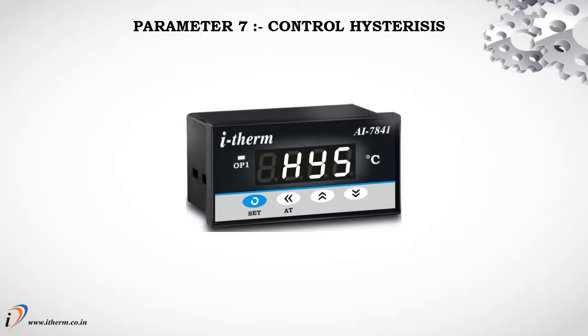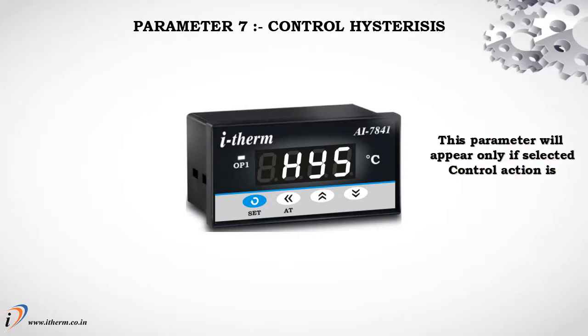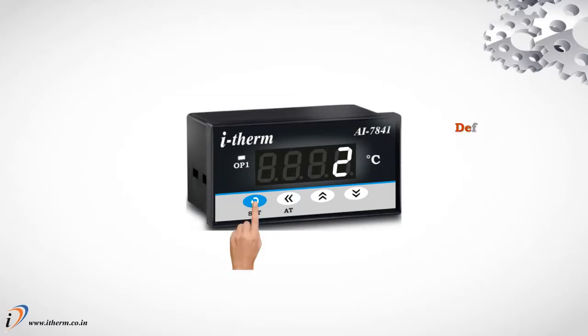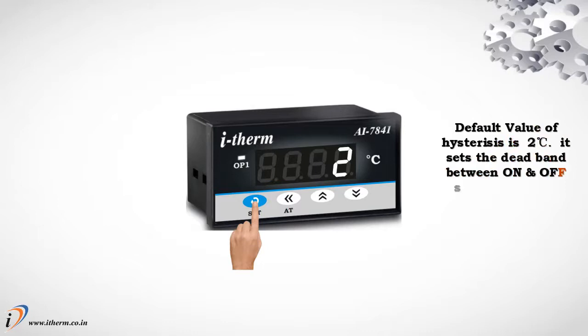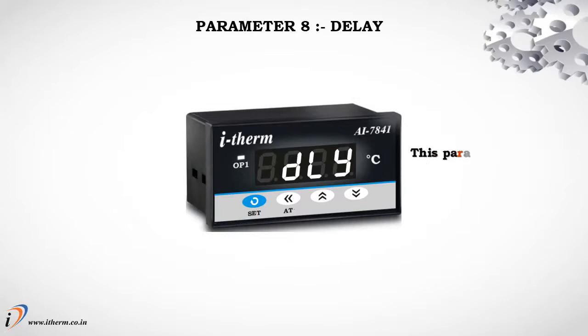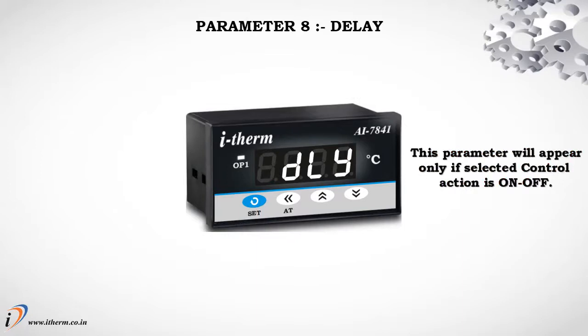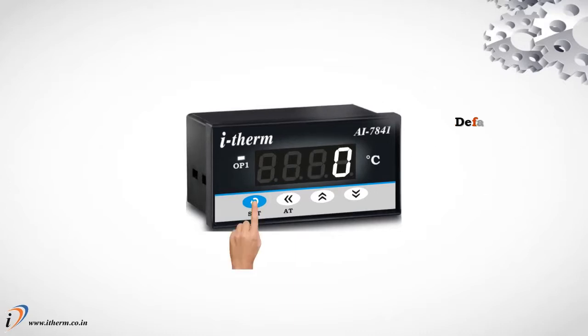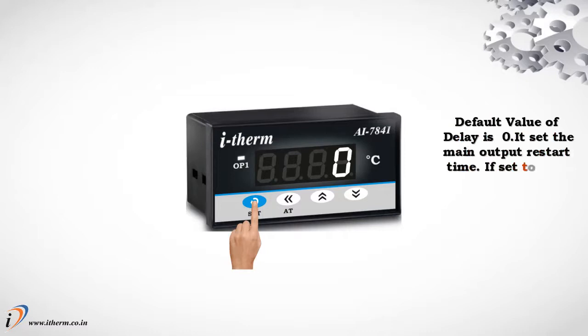Parameter 7, control hysteresis. This parameter will appear only if selected control action is on-off. Default value of hysteresis is 2 degrees centigrade. It sets the dead band between on and off switching of the output. Parameter 8, delay. This parameter will appear only if selected control action is on-off. Default value of delay is 0. It sets the main output restart time. If set to 0, output will be switched without delay.